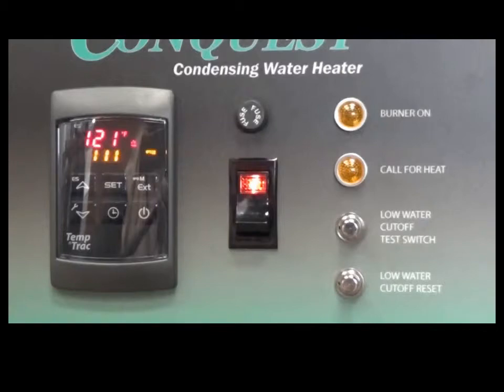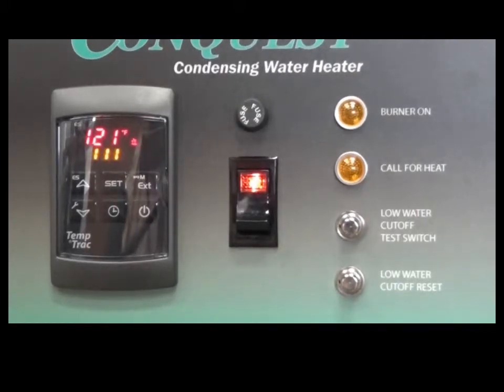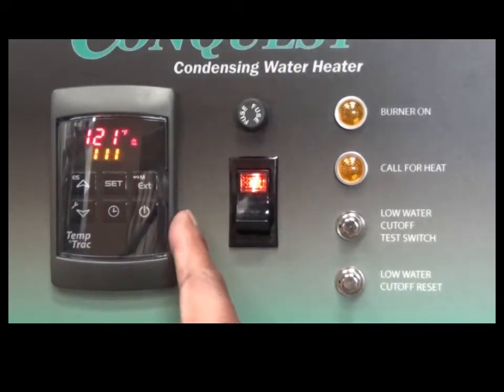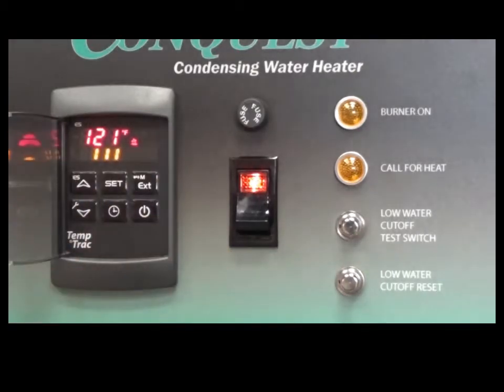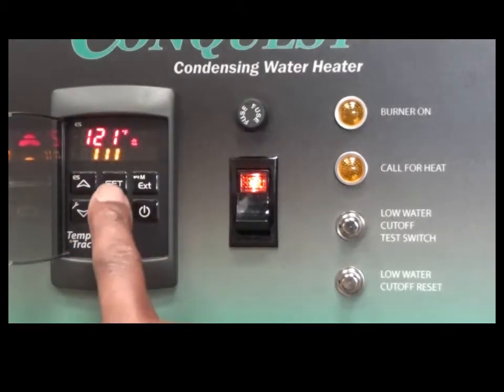Now we'll review the home screen display and control button functions with the water heater satisfied with the factory set point of 120 degrees Fahrenheit. We see that the upper display shows that the temperature sensed at the top of the tank is 121 degrees. The lower display shows the temperature sensed in the middle of the tank is 111 degrees. The temperature icon is illuminated, which indicates that the Temptrac internal output 3 pump relay is energized. This occurs whenever the temperature sensed at the middle of the tank is 5 degrees or more below the temperature set point. The intra-tank circulating pump is then energized through Temptrac terminals 8 and 9.